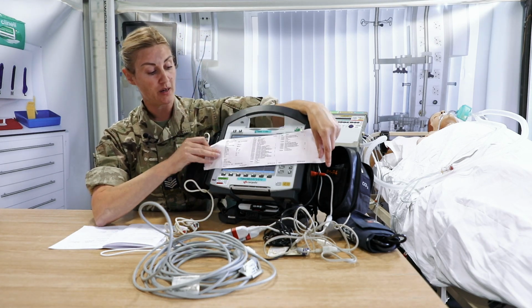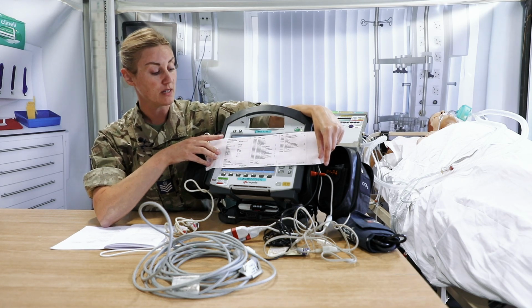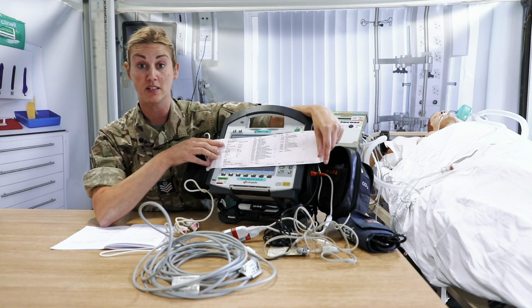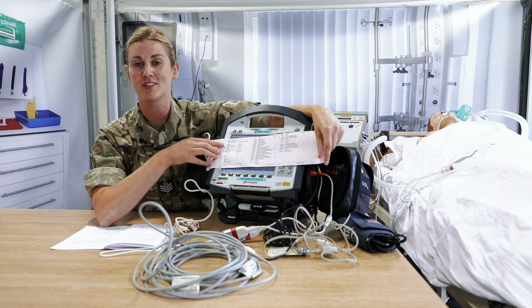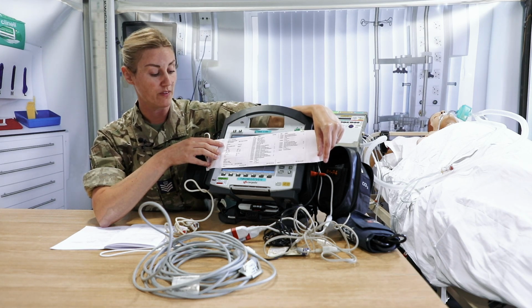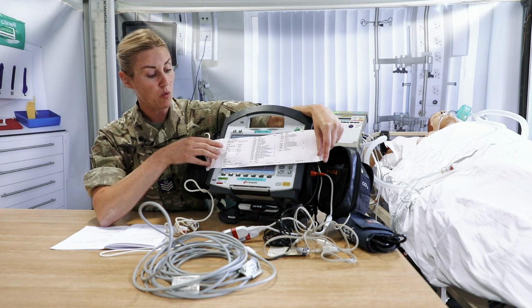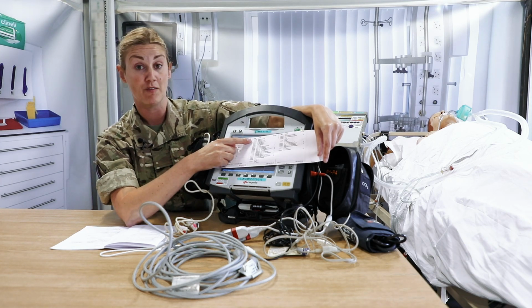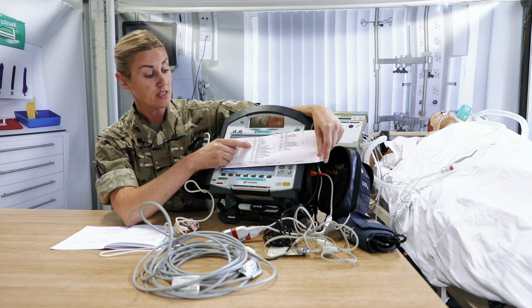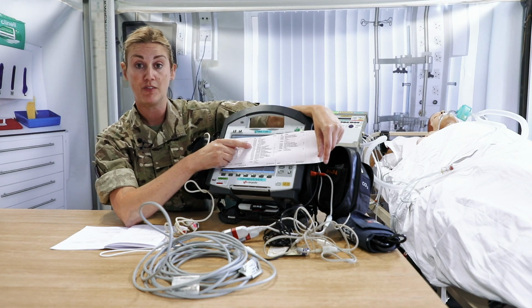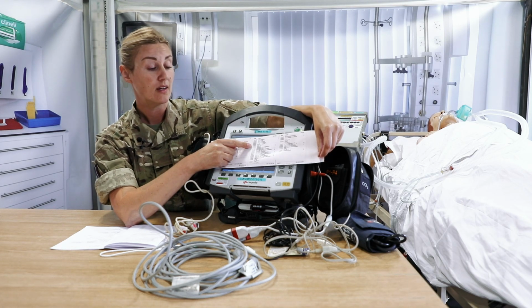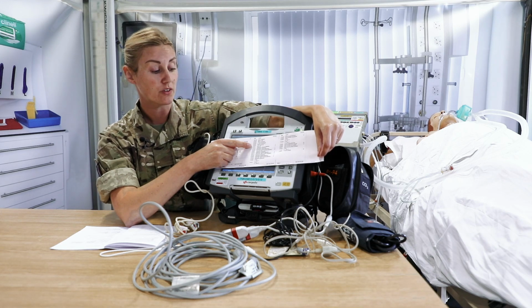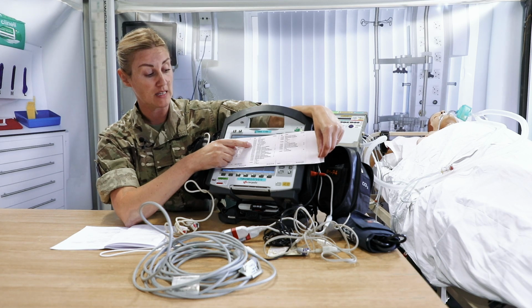On this piece of paper, we're going to check a few things. So we're going to start off by checking that the date and time is correct, if you're setting this to Zulu time, or if you're setting it to local time, just to confirm that all of that is correct. And we're going to work our way through these events here. So the first event that we're going to check is that the VT-VF alarm is switched on. Obviously very useful if the patient goes into VT or VF whilst being monitored, so confirm that's on.